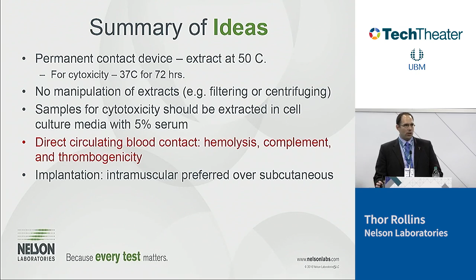Here we go with hemolysis. They, once again, do not follow ISO 10993-4 here, and they say if your device contacts blood, they recommend, doesn't matter how long or what type of blood it contacts, you have to do hemolysis, complement, and thrombogenicity. So if your device contacts blood, we're talking about circulating blood, not blood in a surgical site, but if it's contacting circulating blood, then we have to test for all those blood endpoints. And that's one that's different. Implantation, intramuscular is preferred over subcutaneous. So those are some of the things that this new guidance document has put out for biocompatibility.